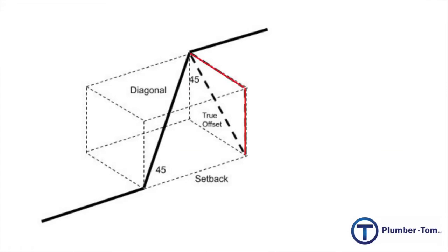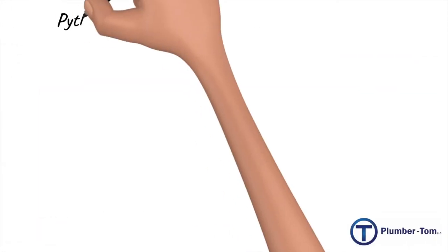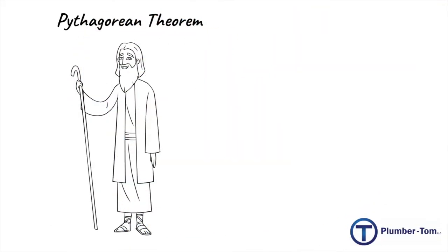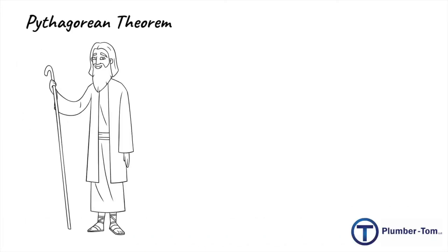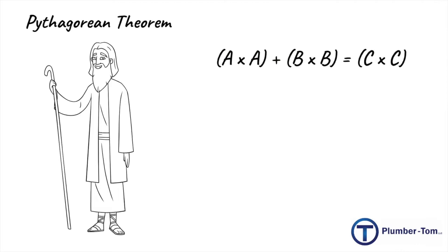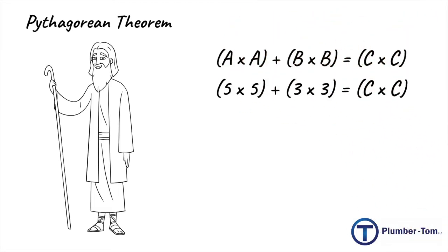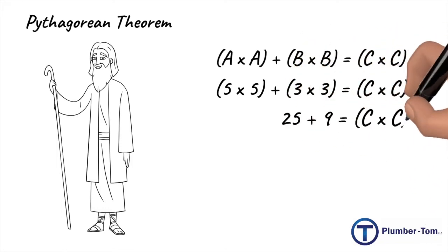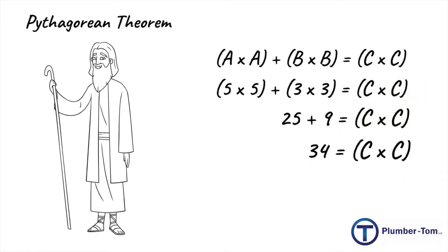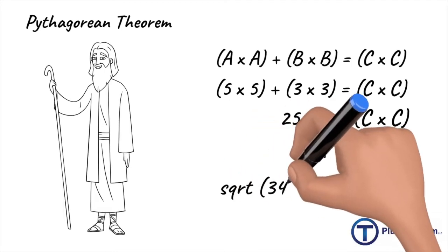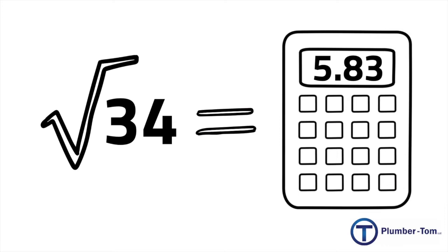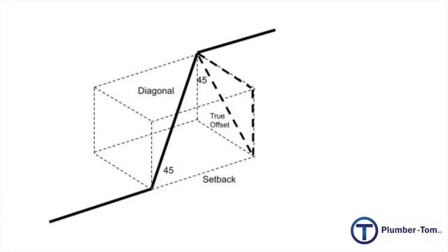With that understanding, let's calculate a rolling offset with an offset of 5 inches and a rise of 3 inches. In order to do this, we will need to use the Pythagorean theorem, which states that a² + b² = c². So with that as our starting point: 5 × 5 + 3 × 3 = c × c. That gives us 25 + 9 = c², so 34 = c². To find c, we take the square root of both sides — using a calculator, the square root of 34 gives us c = 5.83.